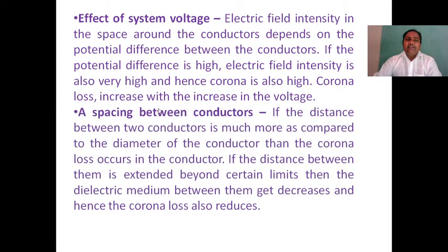Finally, the spacing between conductors. If the distance between two conductors is not much more as compared to the diameter of the conductor, then corona loss occurs in the conductor. If the distance between them is extended beyond certain limits, then the dielectric stress between them decreases, and hence the corona loss also reduces. This way the spacing between conductors affects the corona loss.